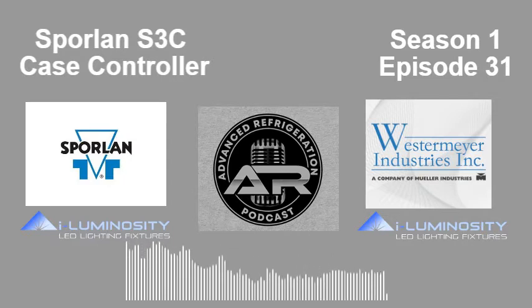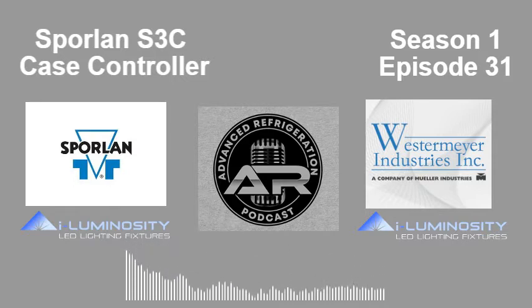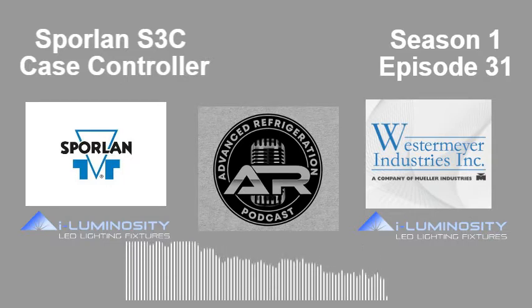So that's the package. An S3C case controller, the display module, which you have to have along with the controller. The valve module is kind of optional. You utilize a valve module only if you need it, and you can connect up to 2 valve modules to one case controller. And just so I'm making sure I got this right, if I'm not mistaken, the program is actually in the display module, correct?